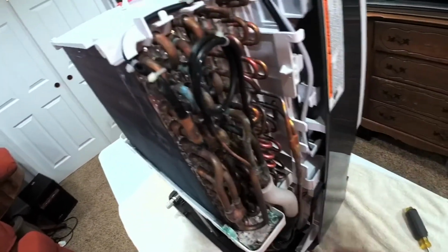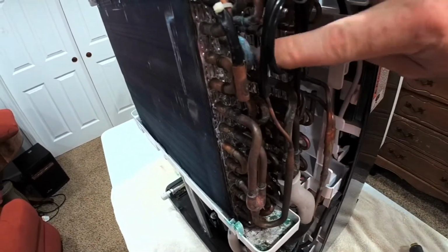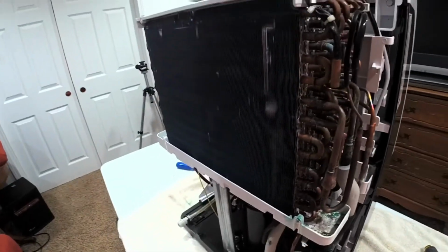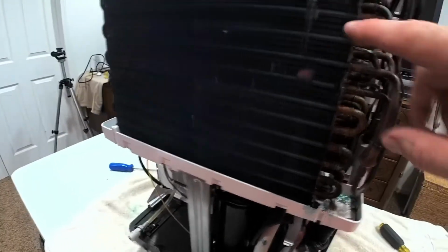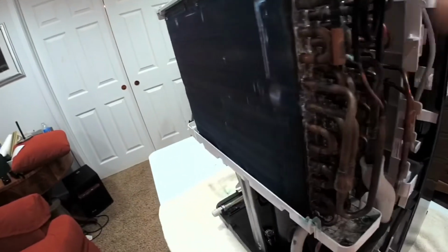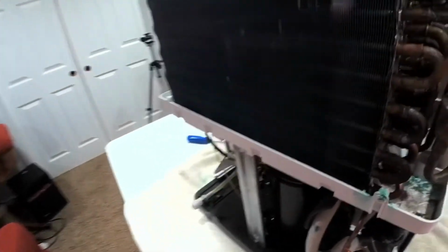But it's possible that maybe one of these is leaking just a little bit. Usually the green is generally an oxidation. It just happens with copper and water and stuff like that, chemical reactions, but there could be a leak somewhere in here. Usually there's a discoloration. See how this side's all blue and this side is all silver, which could mean it's somewhere along in there. It could be just a hair pin hole of some sort that is a slow leak.